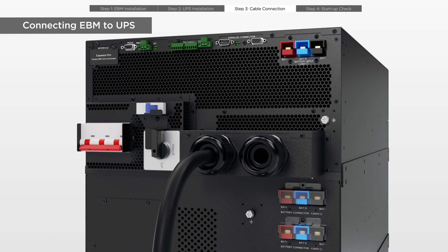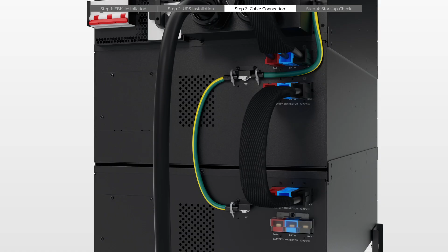Remove the battery PVC protective cover of the EBM. Connect the battery cable to the UPS and EBM. Connect the ground wire to the UPS and EBM. Secure the fixed plate to the UPS with 2 black truss screws, fasten with a cable tie, then repeat for the EBM. Repeat the steps to connect the battery cable and ground wire for additional EBMs.